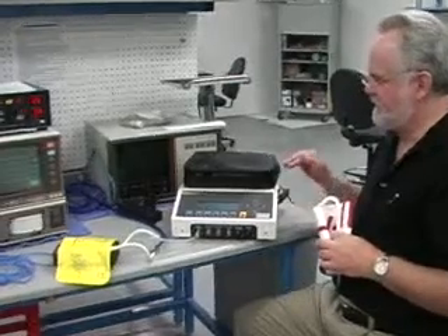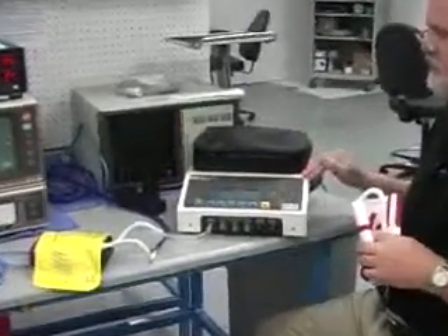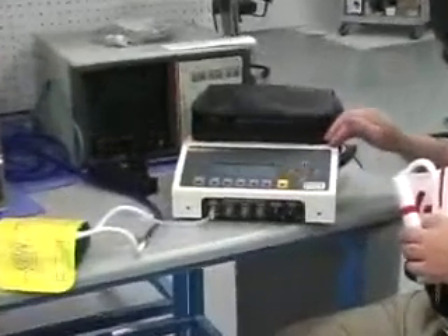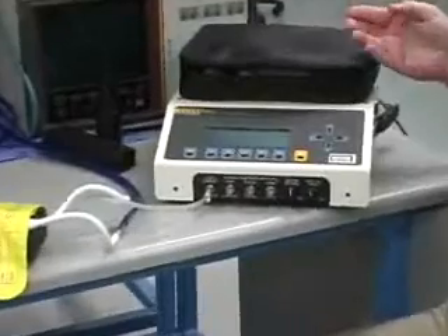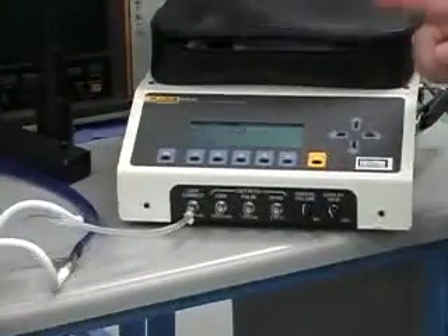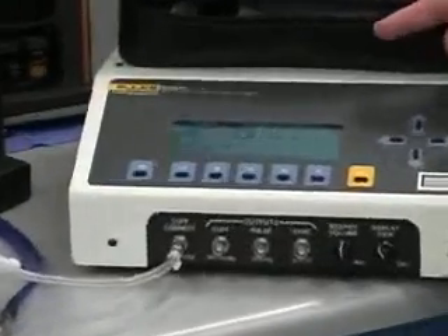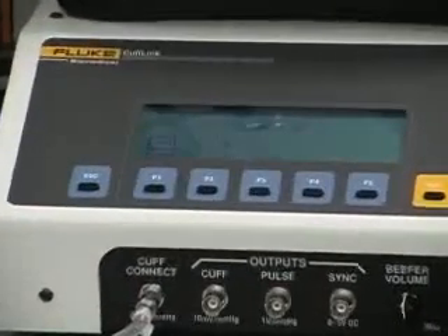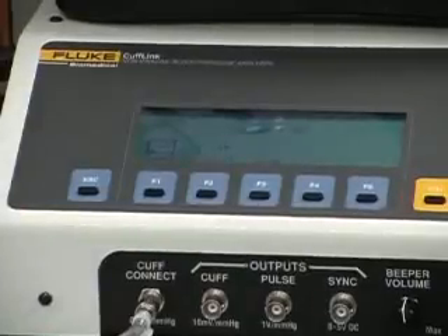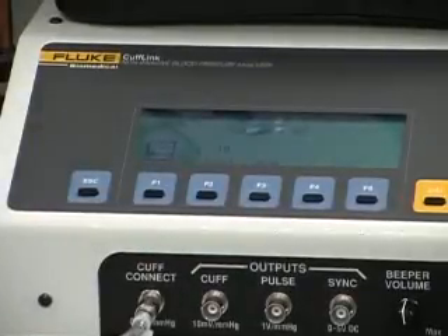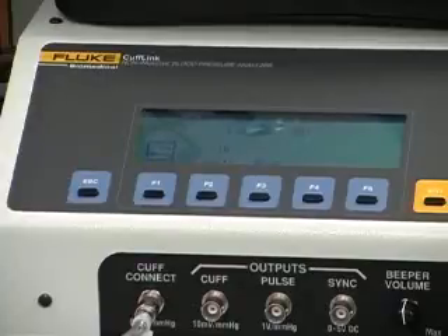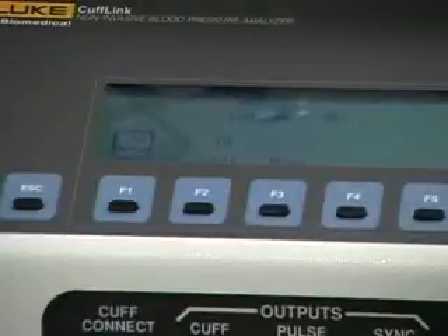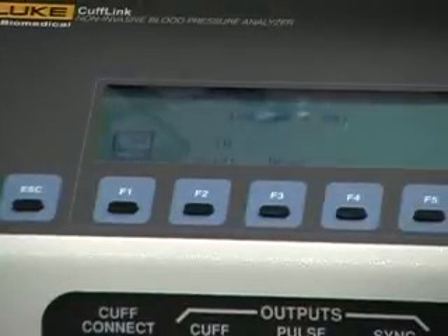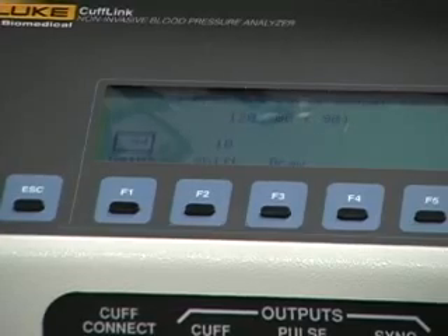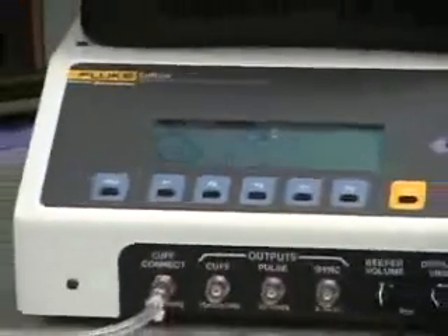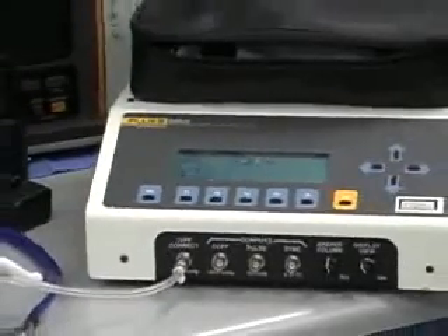Okay, so that gives you the ability to adjust the pressure levels dynamically, so you can take our 120/80 and add pressure to it, or take pressure away from it. And you can also run either a strong pulse, a normal pulse, or a weak pulse, simulating different patient conditions. So imagine too, if you're testing athletes or whatever, you can make sure that it can work there too with the higher pulse amplitudes. Great. Any questions on either non-invasive blood pressure or the Cufflink? It's really simple. That's very straightforward.